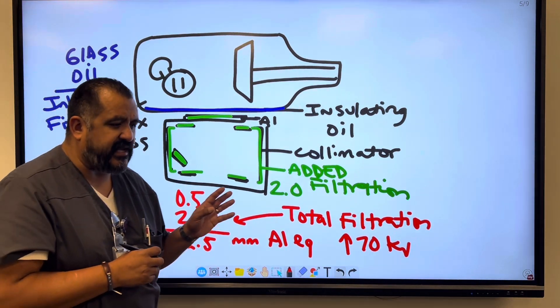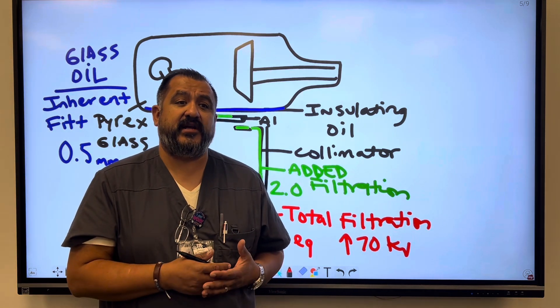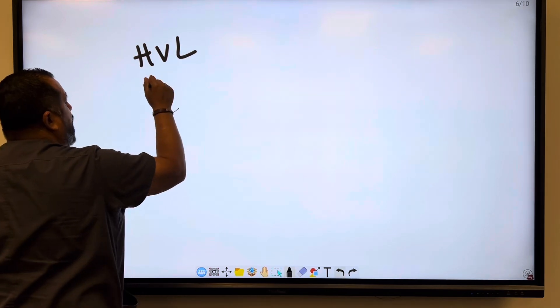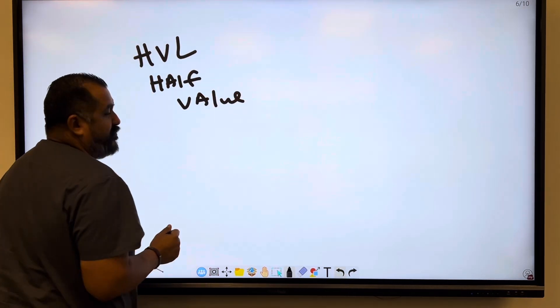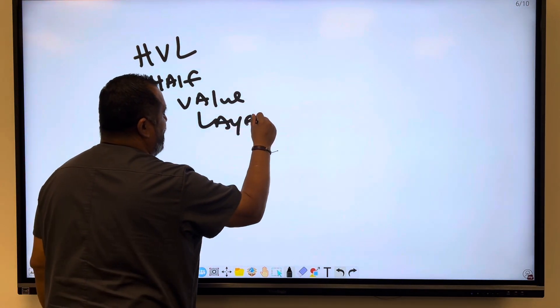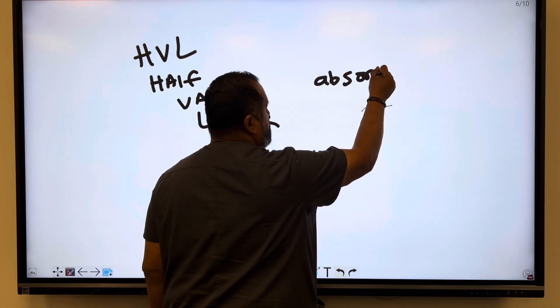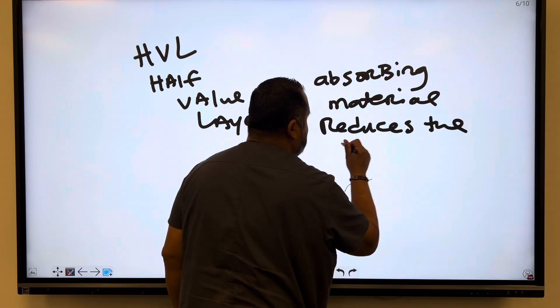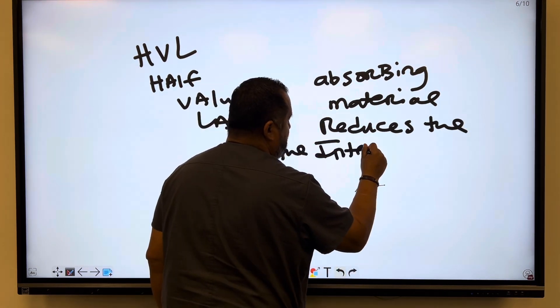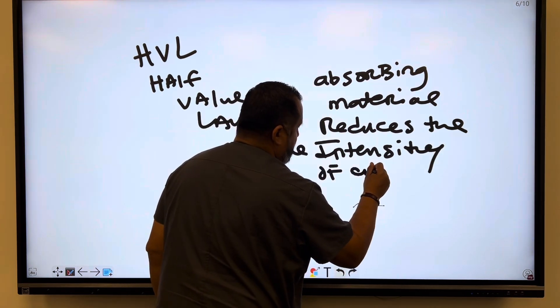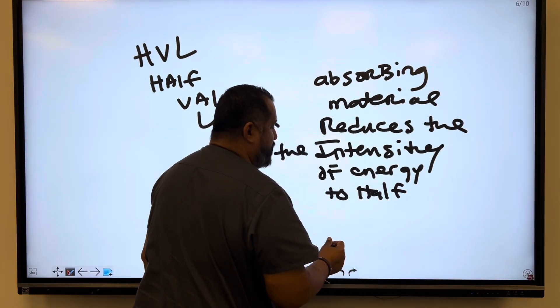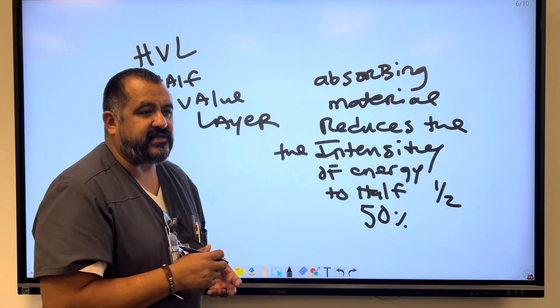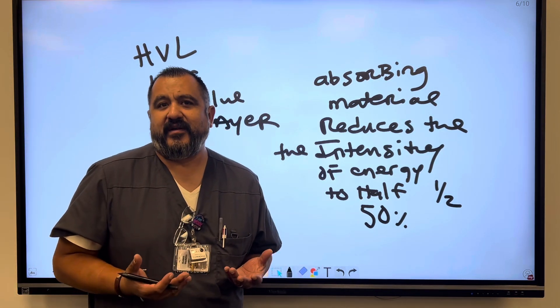Now there's another term that's in the textbook that goes by HVL. So filtration sometimes is related to what's called HVL. So HVL stands for half value layer. So half value layer is any absorbing material that reduces the intensity, the intensity of energy to half the original value. So instead of saying half like this, you can say that it reduces it by 50% of the value. So a half value layer is any absorbing material that reduces the intensity of radiation to half.